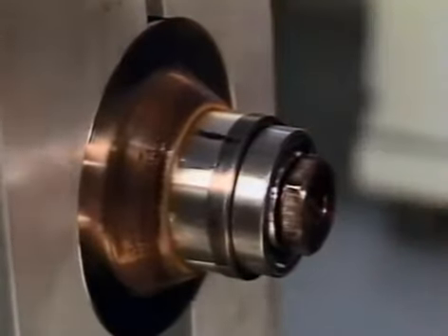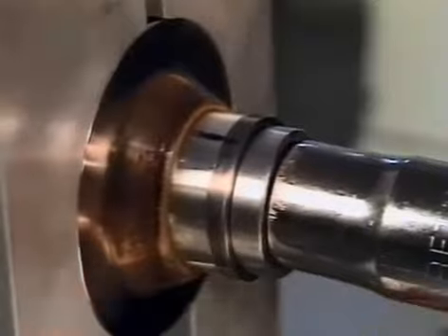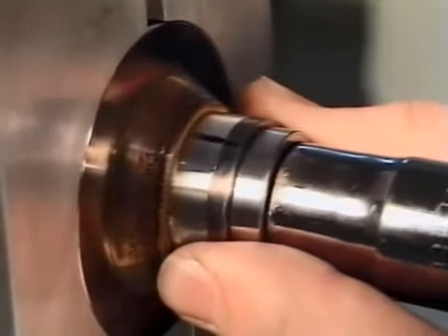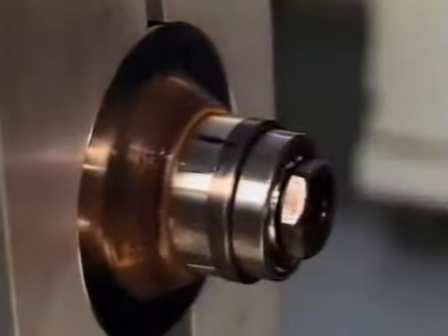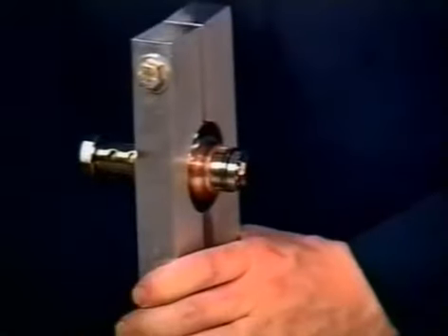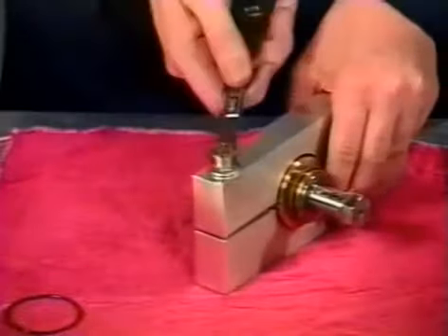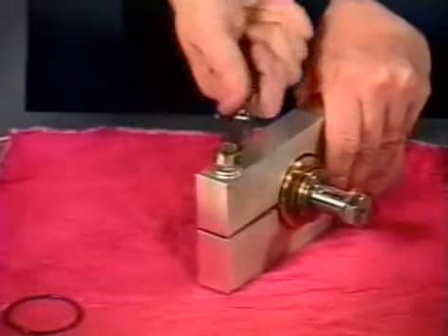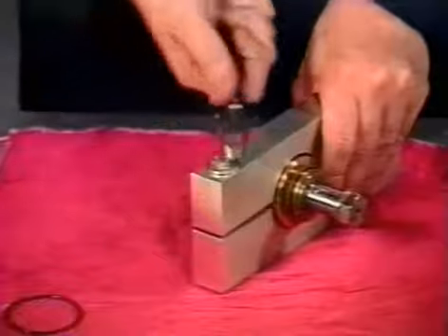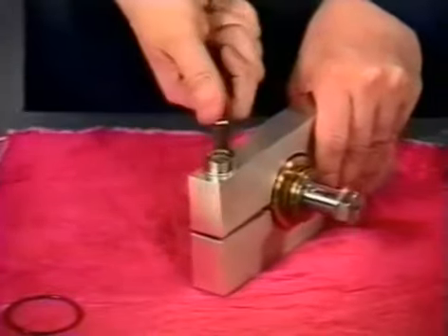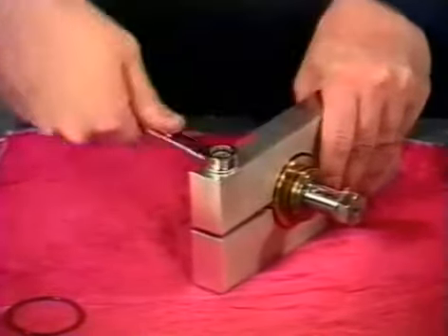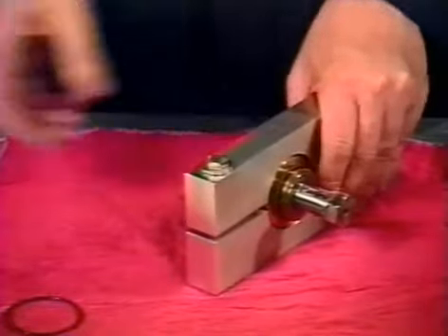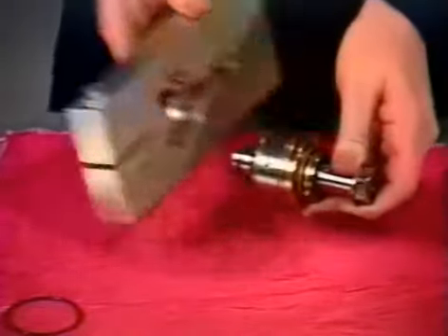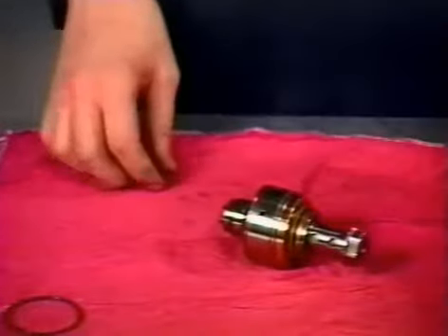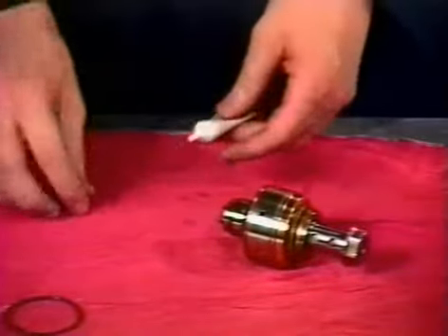Torque the inlet screw to 120 inch-pounds. Do not use a foot-pound torque wrench to torque the inlet screw, or you might damage the inlet screw. Remove the check valve from the check valve clamp. Lubricate, and install the O-ring on the outside of the check valve body.